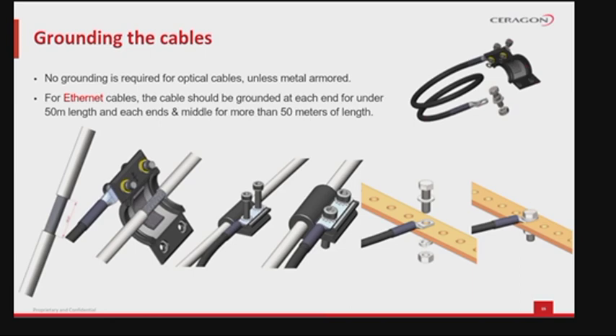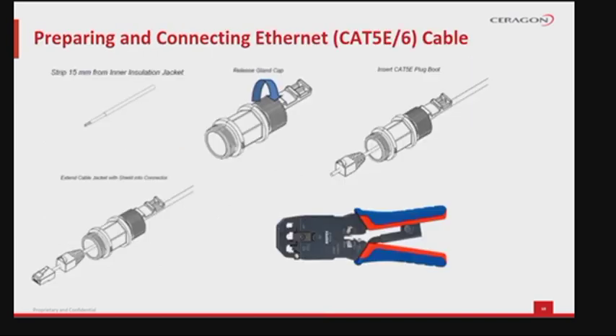As per the standard, Ethernet cable can be run to a maximum length of 100 meters. Ethernet cable needs grounding near the two ends for distances smaller than 50 meters, and grounding near the two ends and once in the middle for lengths of more than 50 meters. Lightning arresters can also be used to prevent the action of high voltages on Ethernet Cat5 cables. This slide shows how to prepare and connect the Ethernet Cat5 or Cat6 cable.